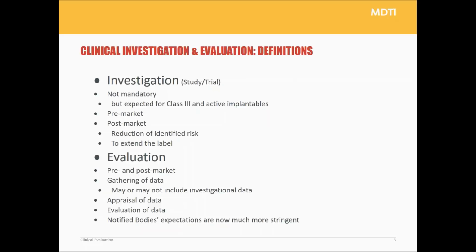And remember, an investigation is not mandatory, but they are expected for class 3 and active implantables and any device that is claiming some sort of novelty, and we'll come on to equivalence in a few minutes. So investigations can take place pre-market, and very often do take place pre-market, even for class 1 devices, in order to get the CE mark.